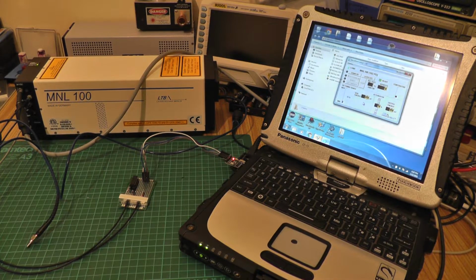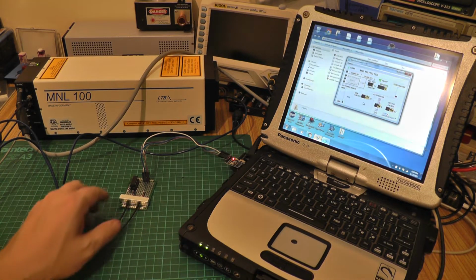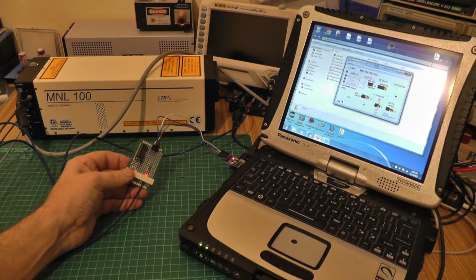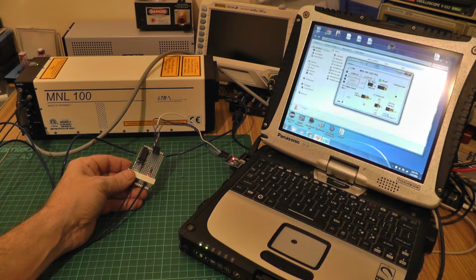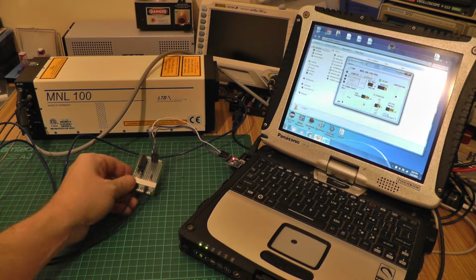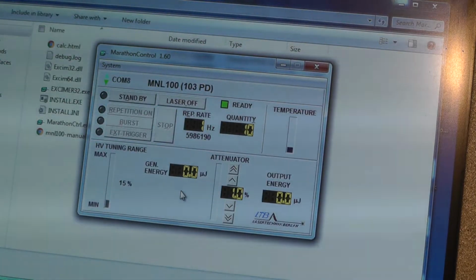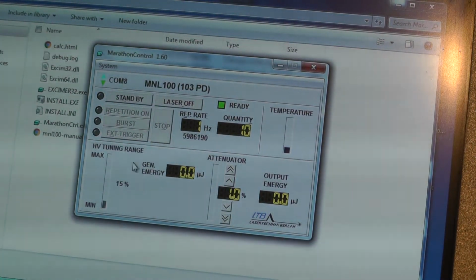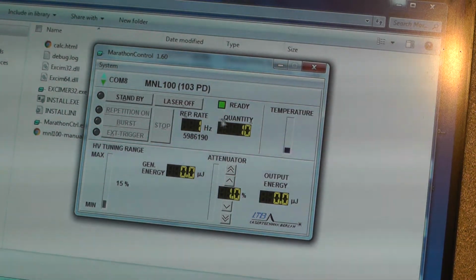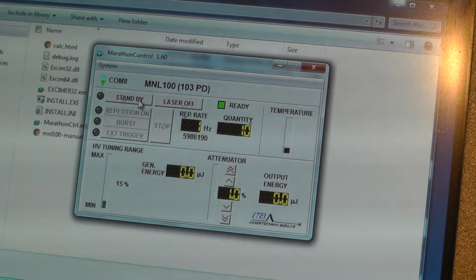So I've hooked the laptop up to the laser using my hacked up fibre optic RS-232 connection. So let's fire this up and take a look. So this is the Marathon control software that you can get off the manufacturer's websites. There's a number of things that we can do in here. We can switch the laser on into standby first of all, and you might be able to hear some clicking in the background as the pre-ionizers start up.